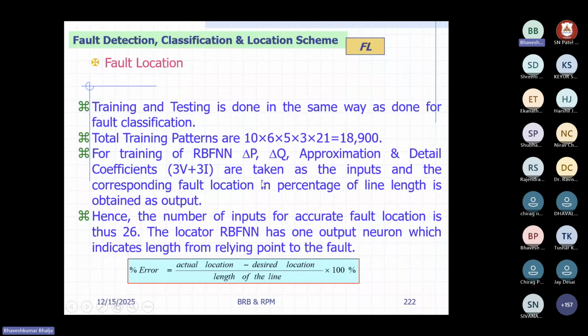Now fault location. Once you have done the classification of which type of fault has occurred, the next part is to calculate the location of the fault. Similarly, you can use the same type of data and training patterns, normalize it, and give it to the other type of algorithm. Then you can calculate the percentage error, which is actual location minus desired location, divided by the length of the line, that is 128 kilometers in this case, multiplied by 100, so you get the error in percentage.